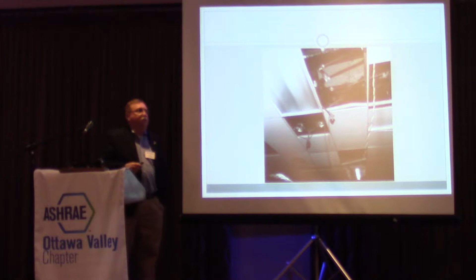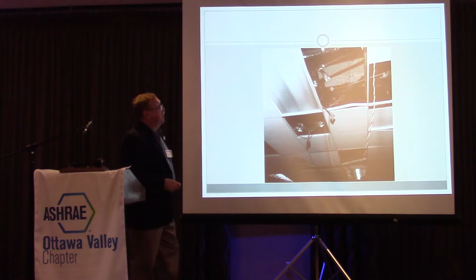Here's one from SeaTac, Seattle-Tacoma. I was working there and in the airport the day we had an earthquake. All the sprinkler pipes fell out because they were all on C-clamps, just clamped onto the side of a purlin. When the earthquake came, it just popped off the side of the purlin, and the whole system went down. NFPA has now changed the code so all sprinkler pipe must have a retaining strap so it can't do that, and the US building code is finally adding that requirement in its last cycle, requiring some form of retaining strap so it doesn't pop off.